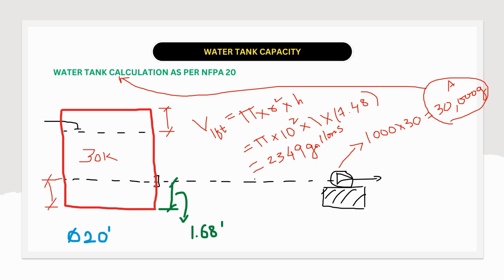Apart from that, you can see from this figure we have drawn a center line and below this center line we have assumed 1.68 feet to the bottom of the tank. Further assuming that minimum water level should be approximately equal to the center line of the suction pipe to prevent fire pump cavitation. So we need to add this volume of water as well to these two volumes.